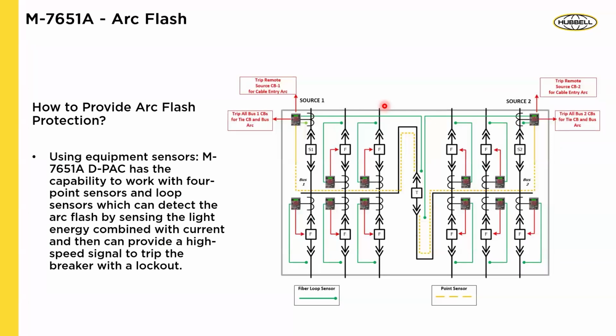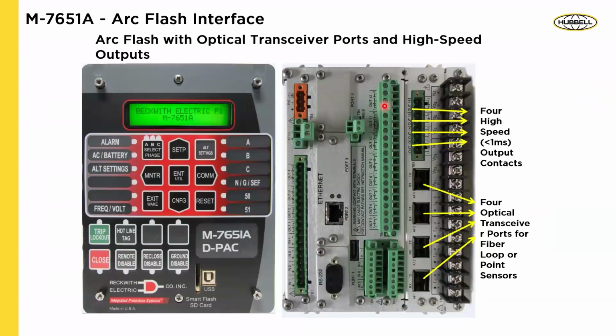Arc flash, right? So we have arc flash in the 7651A. And then using 4 optical sensors, it has point sensors and loop sensors. And depending on the configuration, you could use your loop sensor for the buses. And then if there's hotspot areas, you could put the point sensors there. Just at the back of the relay, you could see those are the inputs for the arc flash. That's the high-speed output. And then you have your extended IO, basic IO here, Ethernet port.